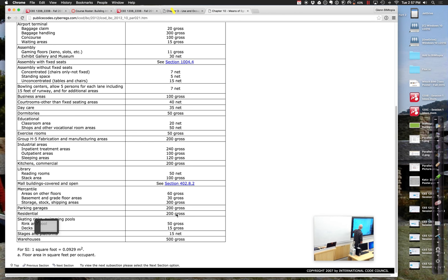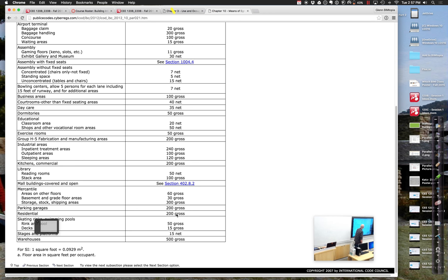For a mercantile space — like a shopping space — at grade level we assume about 30 square feet per person; on other floors, about 60 square feet per person. Think about it: on the ground floor, a lot of people are wandering in and out, while upper floors have fewer people. We divide through by 30 per person to come up with the total occupant load.